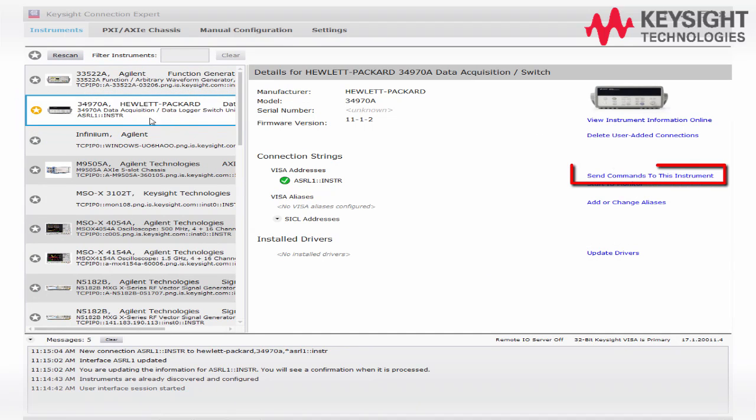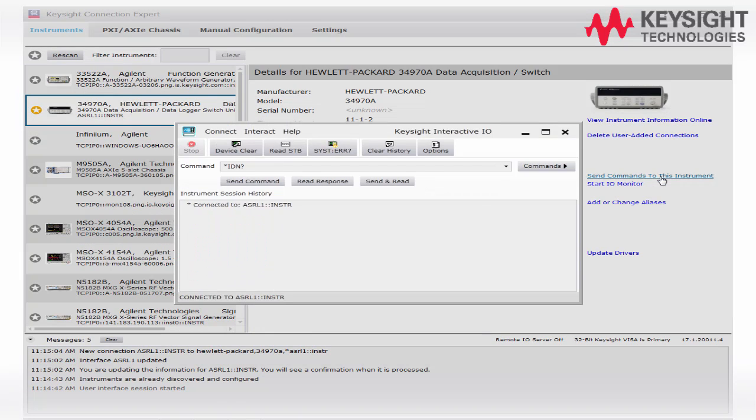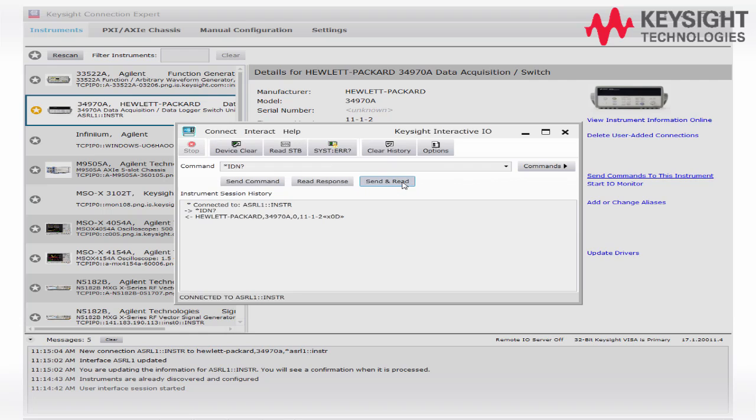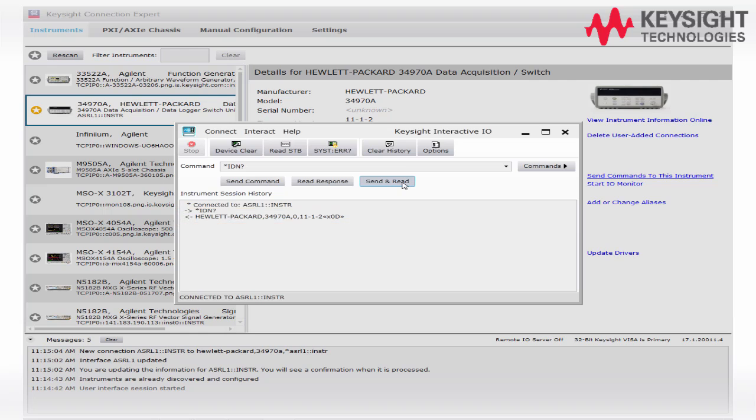Then click on the Send command to this instrument. And then click on the Send and Read button for *IDN?. You will see the communication between 34970A and PC is established once a string returned in the form.